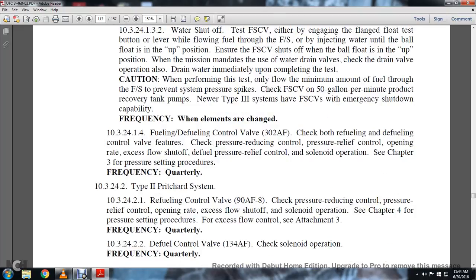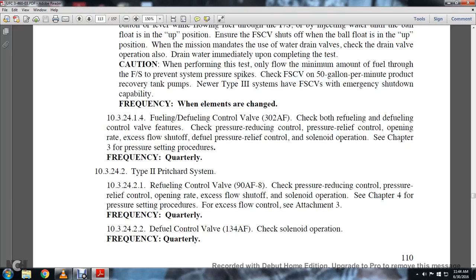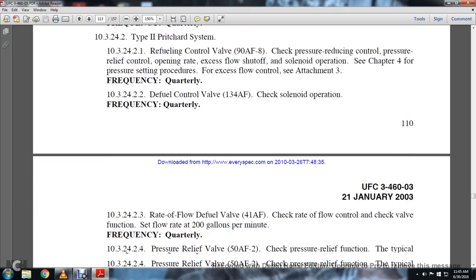Type 2 Pritchard refueling control valve, 90 AF8. Check the pressure reducing control, pressure relief control, opening rate, excess flow shutoff, and solenoid operation. See Chapter 4 for pressure setting procedures for excessive flow control. See attachment 3. Frequency for the refueling control valve is quarterly. Defueling control valve: check the solenoid operation quarterly.